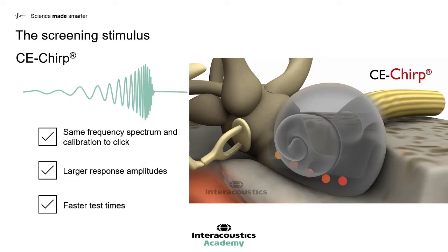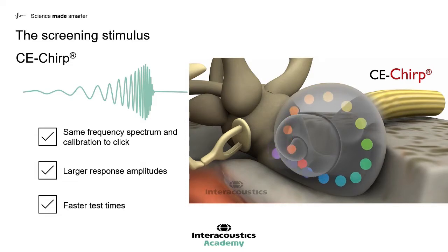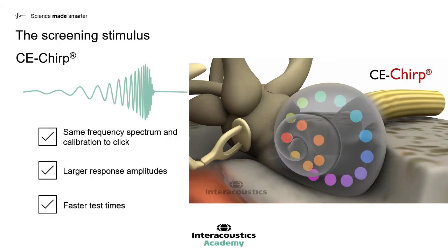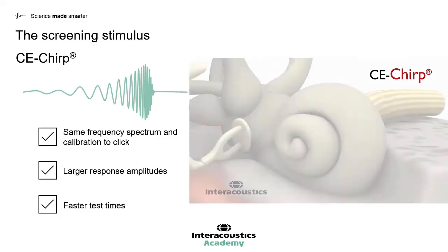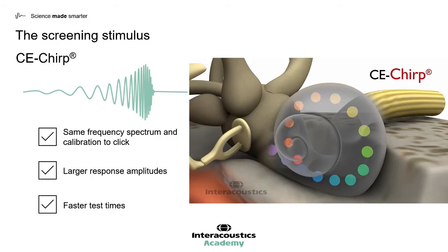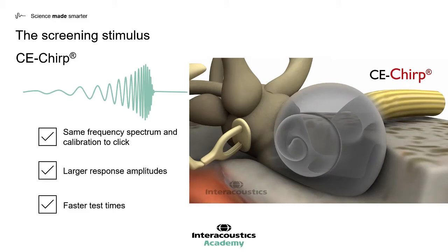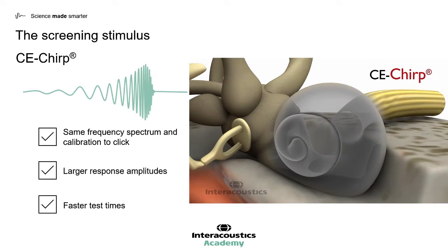The video on the right shows how it works. Instead of delivering all frequencies at the same time to the cochlea, the CE CHIRP does things differently. Firstly, it presents the low frequencies, followed by the mid frequencies, followed by the high frequencies. These then travel along the basilar membrane and reach their respective part at the same time, meaning that when they cause neural firing, this all happens simultaneously, leading to a synchronous response on the nerve, and therefore larger response amplitudes.